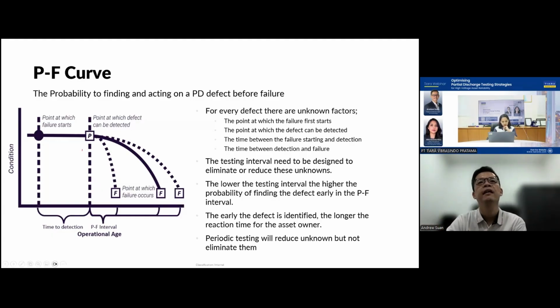It will miss out. The second point is when the defect can actually be detected. But being able to detect and actually being detected are two different things. For example, the defect could be detectable in January, but if you're not there doing your PD survey until June, six months later, you've wasted six months of detection time.